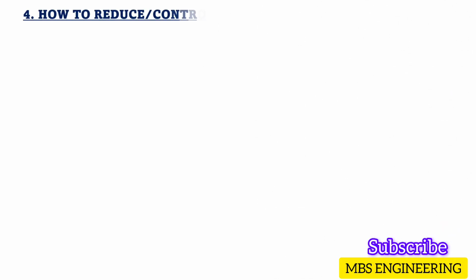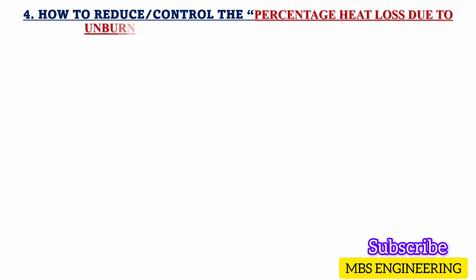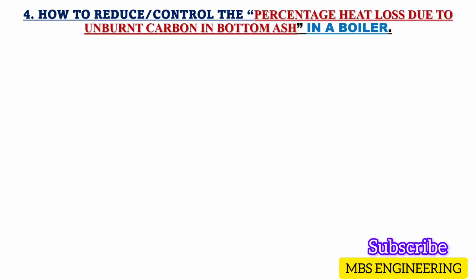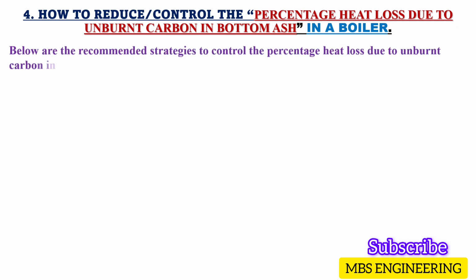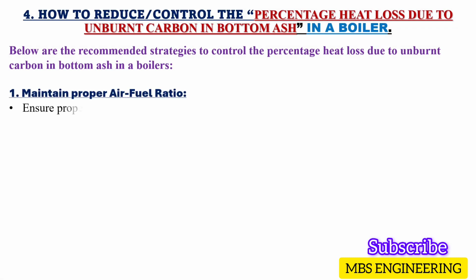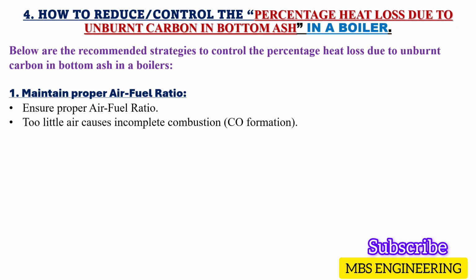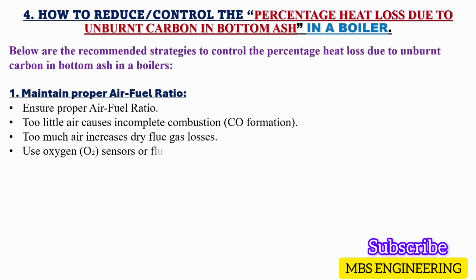Next, we will learn and understand how to control the heat loss due to unburnt carbon in bottom ash in a boiler. Below are the recommended strategies to control the percentage heat loss due to unburnt carbon in bottom ash in a boiler. So, our goal is to minimize this unburnt carbon by improving combustion efficiency. The first recommendation is to reduce the heat loss to maintain proper air-fuel ratio. Ensure proper air-fuel ratio. Too little air causes incomplete combustion, it leads to CO formation. Too much air increases dry flue gas losses. Use oxygen, O2, sensors, or flue gas analyzers to monitor and maintain optimal ratio.